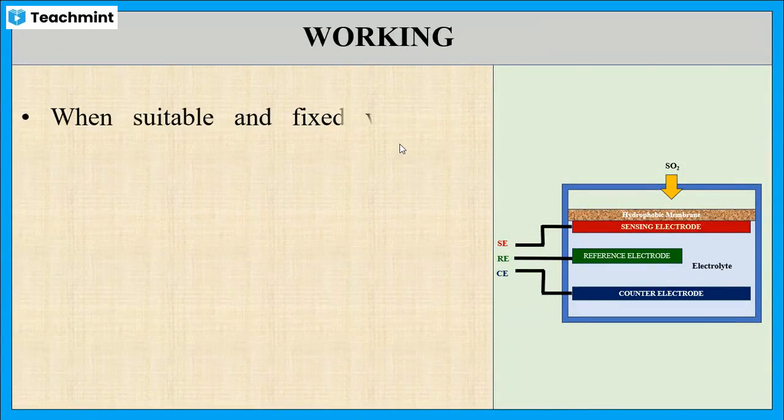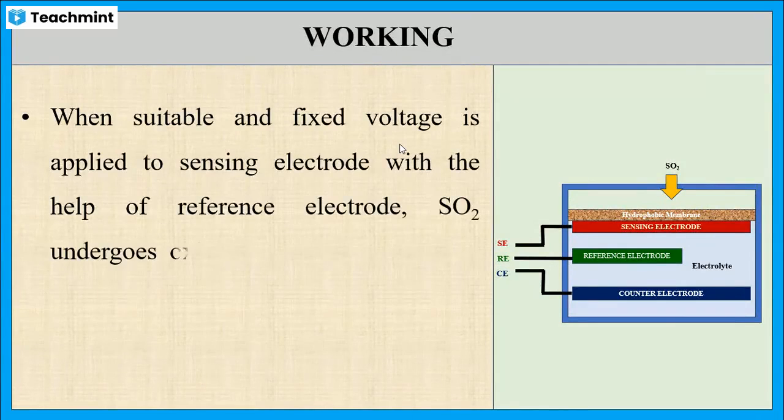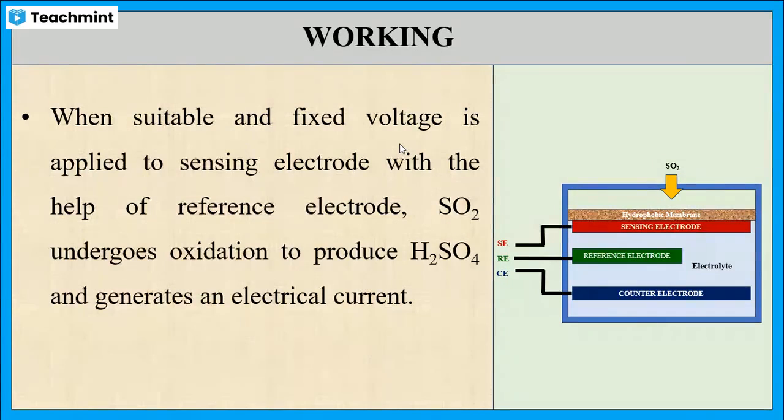When suitable voltage is applied to the working electrode using the reference electrode, then it will oxidize sulfur dioxide to generate an electrical current which is proportional to the concentration of the gas.